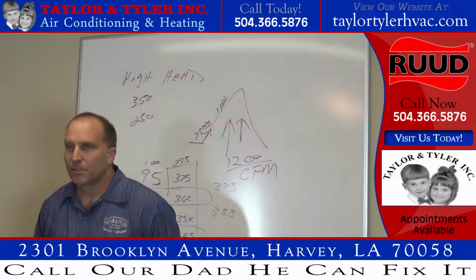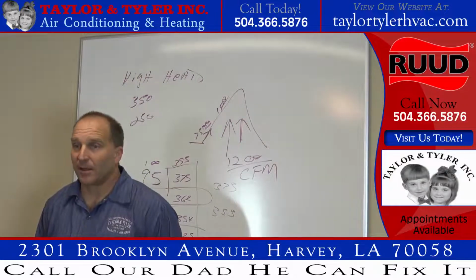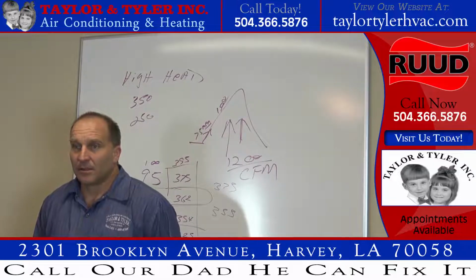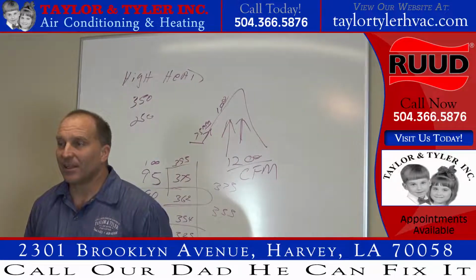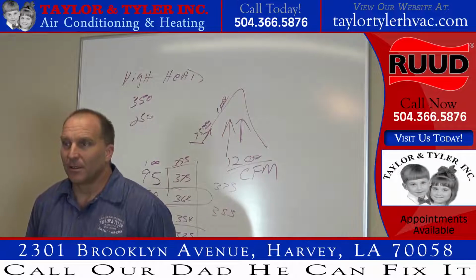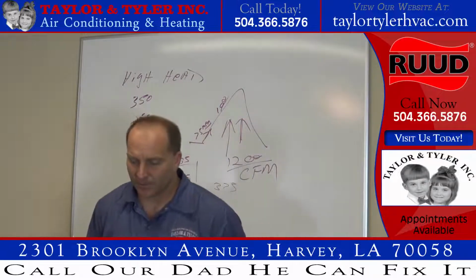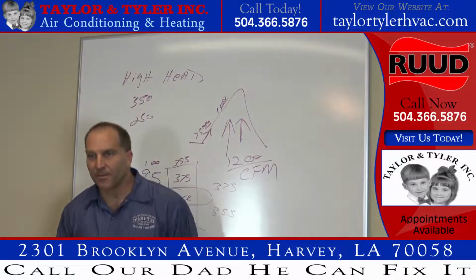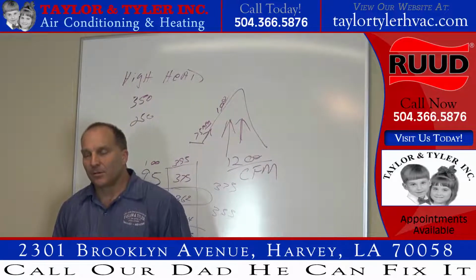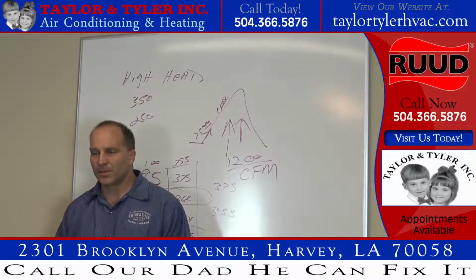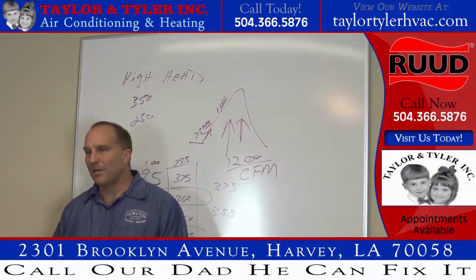So what do I do? I go grab the refrigerant out of the tank, out of my truck. It's low on refrigerant, right? Everything's telling me it's low on refrigerant. Low subcooling, high superheat, low head pressure, low suction pressure. I start adding refrigerant to the system. Keep watching my head pressure, watching my suction pressure, and I'm like, man, it's not changing. What's going on here? Keep adding refrigerant to it.